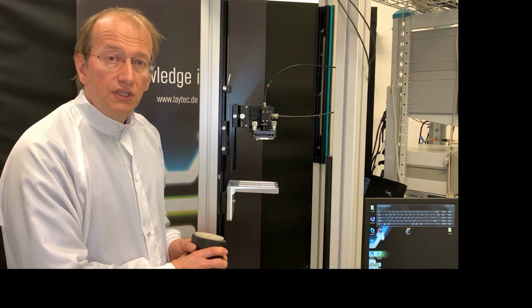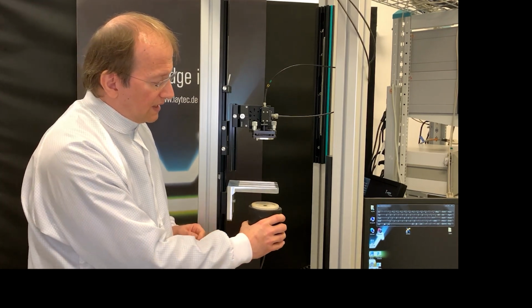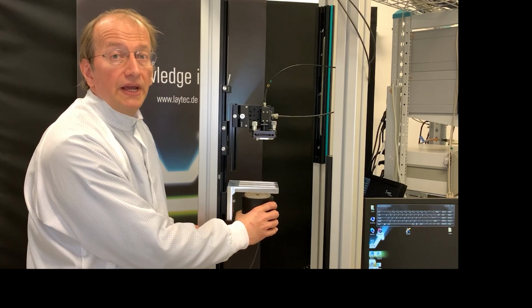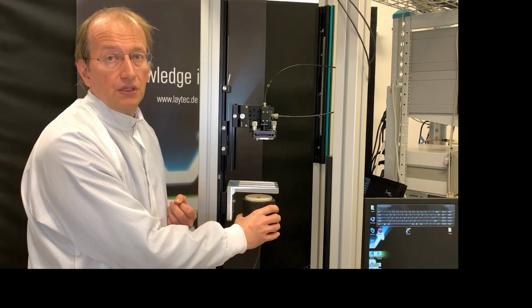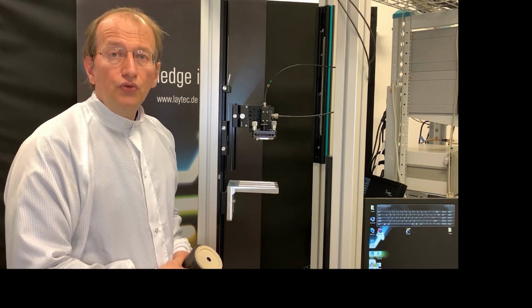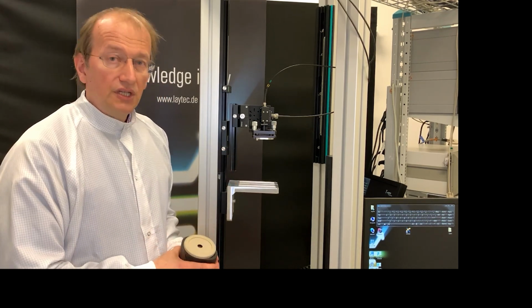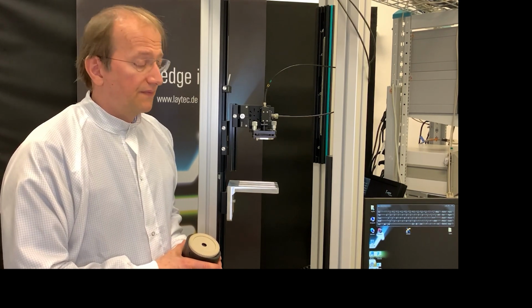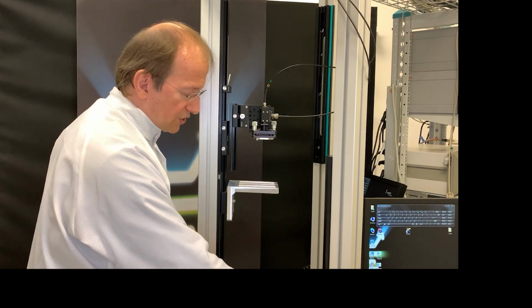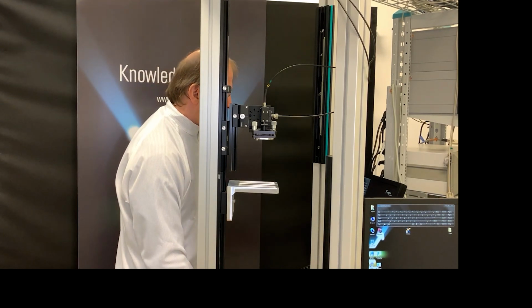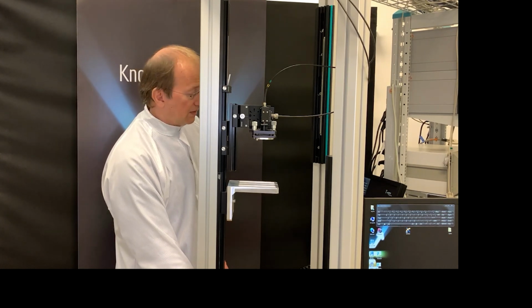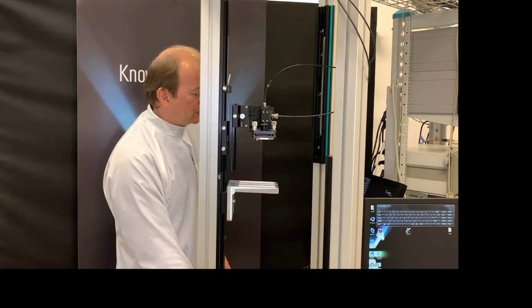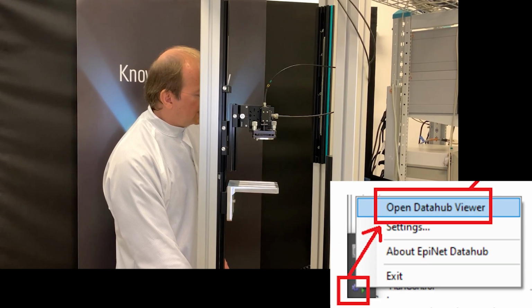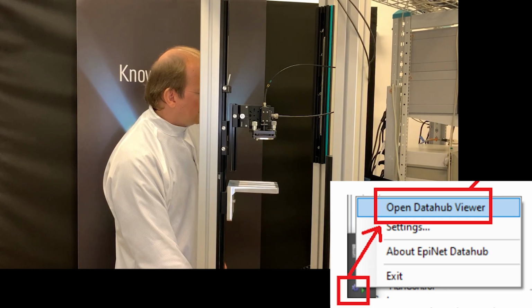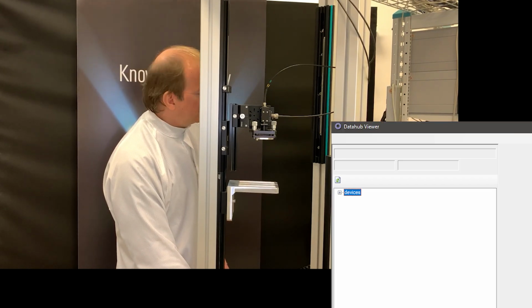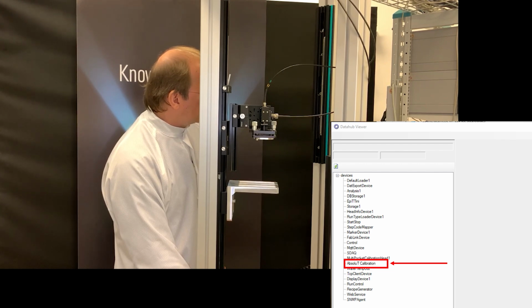As we already talked about in the first part, we have to place the AbsoluT device in the optical axis, so below your sealing hole or viewport hole. And in order to do this, we need interaction. Just by hand, that would be too difficult. Therefore, we have in our EpiNet Data Hub a matching tool. So we will start the Data Hub by going down to this icon in the Windows taskbar. These are these two blue gears and the green triangle, and we select Open Data Hub Viewer. Then we select here Devices, and we scroll a little bit further down, AbsoluT calibration device.